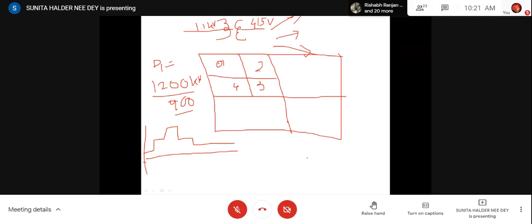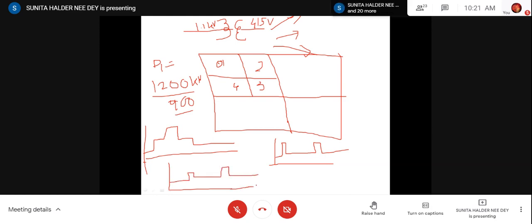Anyway, similarly for D2 there will be another load curve. Say its peak is nearby, like this. Then D4, D3, say it is something different. So you can see, as I have shown, that the maximum demand is happening at a different time span in that block. So in D1, you will decide the transformer size based on this practical maximum demand. For this one, as I have drawn, this should be the maximum. For this one, depending on this peak. For this D3, depending on this peak. Have you understood my point?